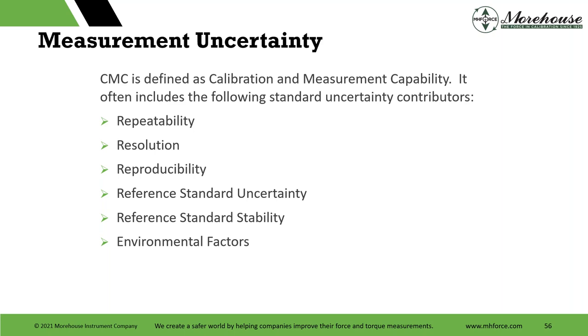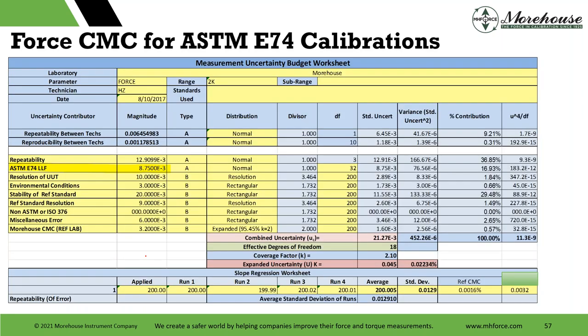So CMC, calibration and measurement capability for UCM. Typically, we're going to look at these per R205. There are more that you would look at. These are the main ones, A2LA. If you're accredited by A2LA, you're going to look at these because you cannot ignore any of these per the R205 document. And we have this online. This is a CMC sheet for force cals.